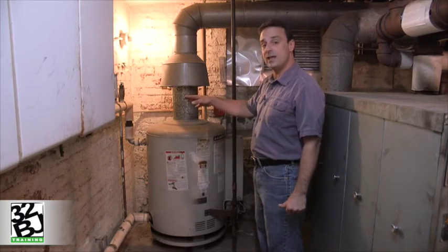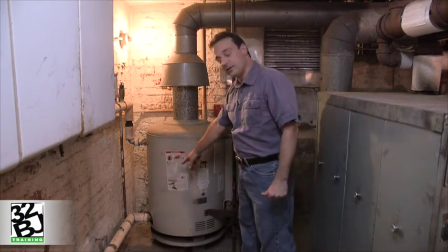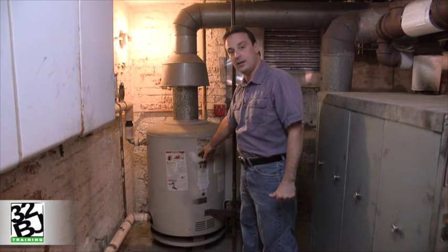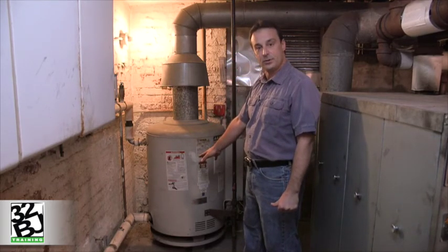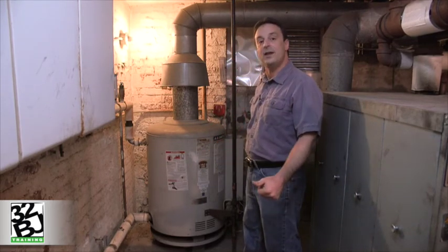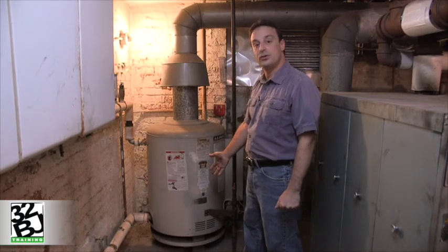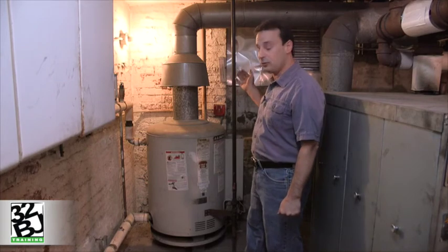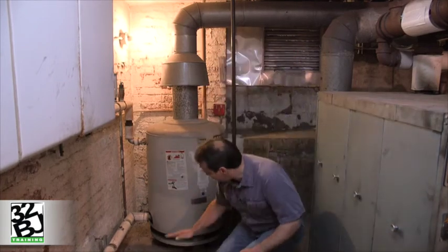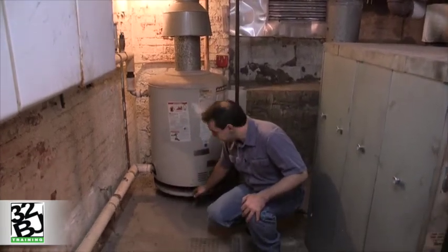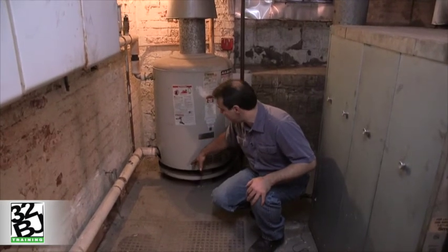As residents use that water, cooler water enters the bottom of the hot water heater, causing a drop in the temperature. The aquastat then initiates the combustion process. It lights the combustion chamber, and through natural draft, air is drawn in to the bottom of the hot water heater to be used for combustion.